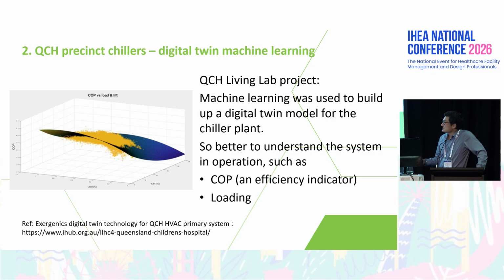That's the COP, the coefficient of performance, an efficiency indicator. The horizontal axis is loading percentage, and the vertical axis is temperature lift for the chilled water. From this chart, we learned our chillers don't really work at highest efficiency when they're 100% loaded - somewhere around 75 to 80% loading is more like our optimum point.